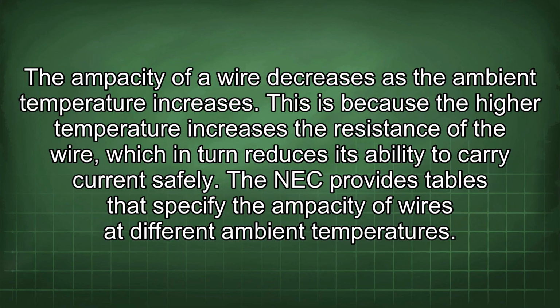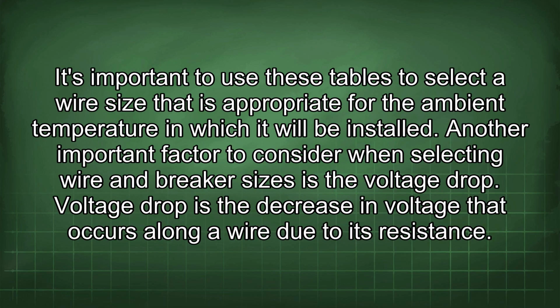This is because the higher temperature increases the resistance of the wire, which in turn reduces its ability to carry current safely. The NEC provides tables that specify the ampacity of wires at different ambient temperatures. It's important to use these tables to select a wire size that is appropriate for the ambient temperature in which it will be installed. Another important factor to consider when selecting wire and breaker sizes is the voltage drop.